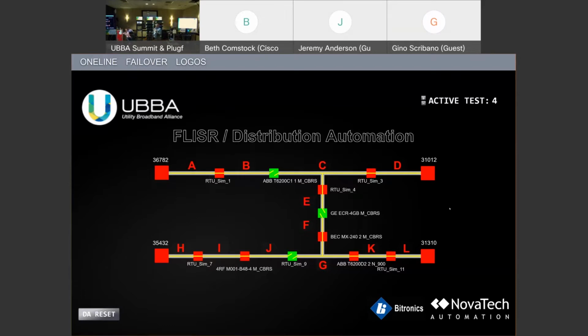In the most simplistic form we see that, we open it, and what the reclosing function did is said, hey, most times when we open up because there's a fault, it's a transient fault. What would be a transient fault that would be out there? A cat, squirrel, snakes, animals on the lines. Those are typically transient. They're there and then they're not there. Trees, limbs and trees hitting the line, they hit it, but they eventually fall off of it on their own.